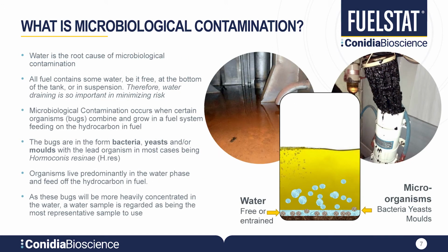Water is the main component in the development of microbiological contamination issues. And whilst regular water draining will help minimize the risk, it is virtually impossible to eradicate it in its entirety, as it occurs naturally dissolved in the fuel and can be added through the likes of condensation whilst being transported through the fuel supply chain.